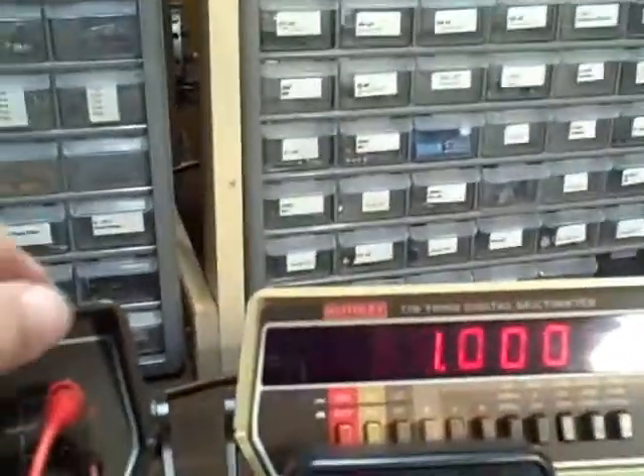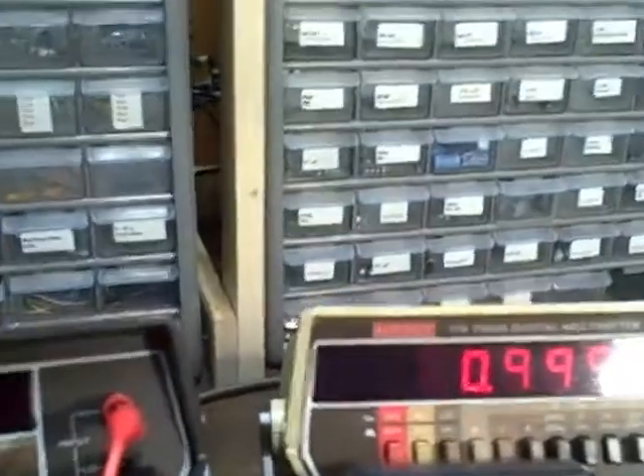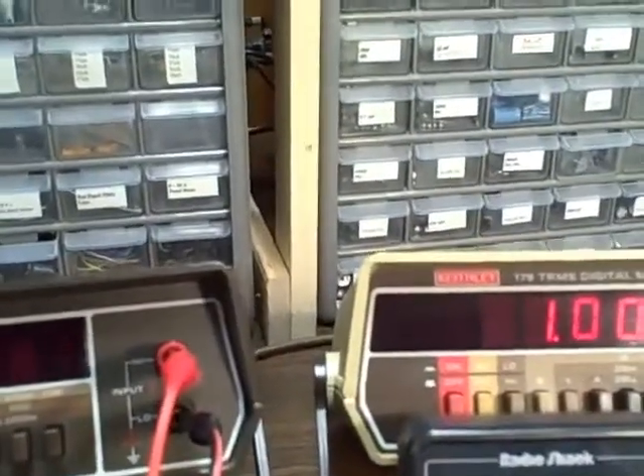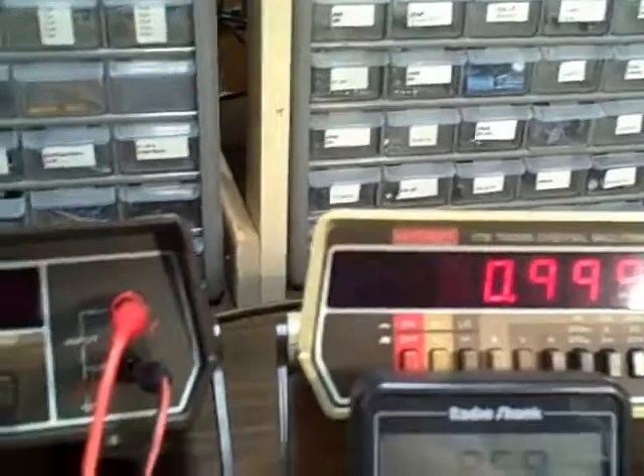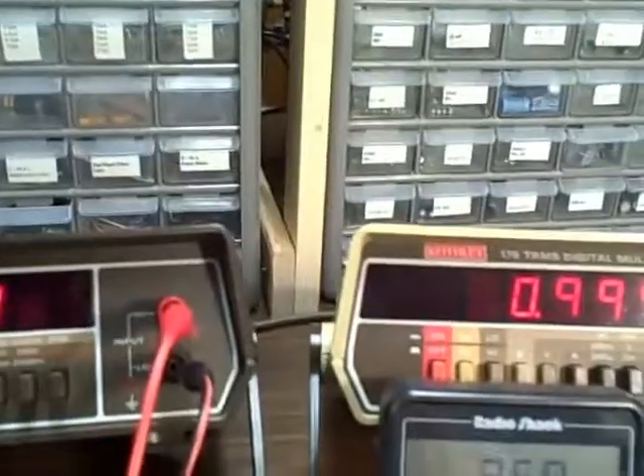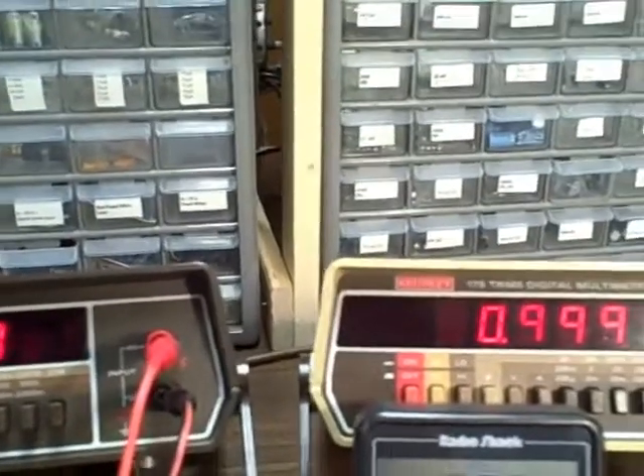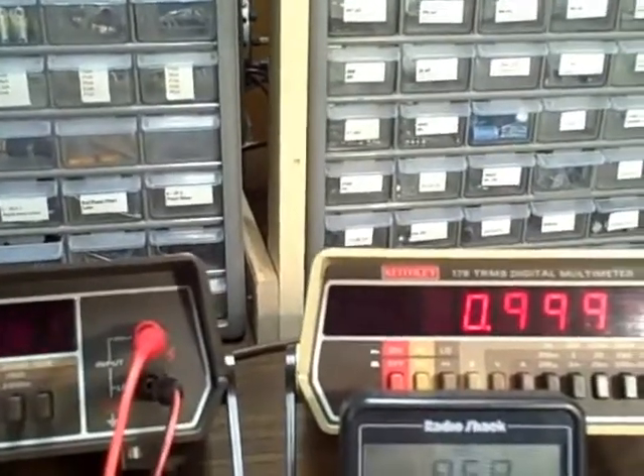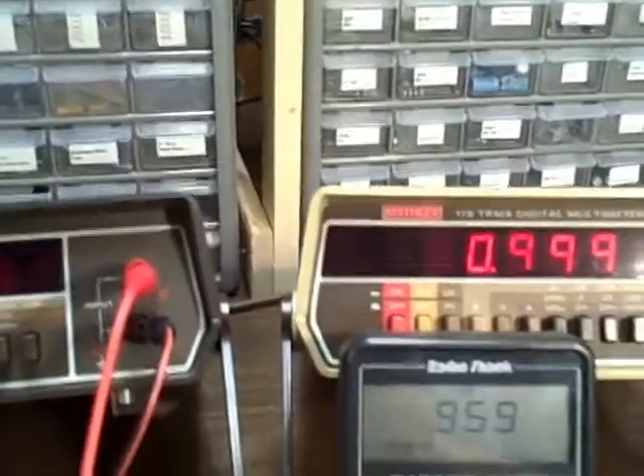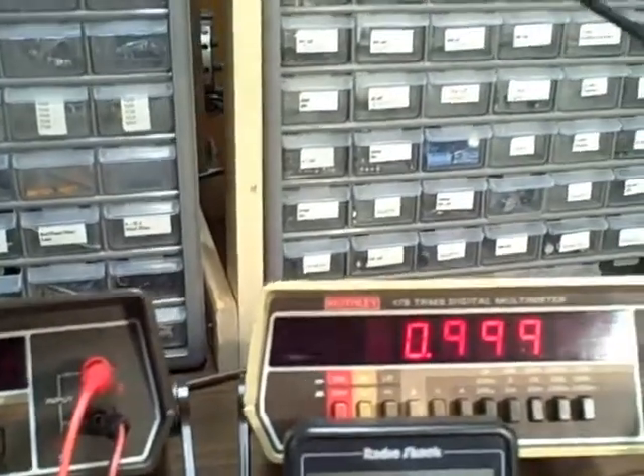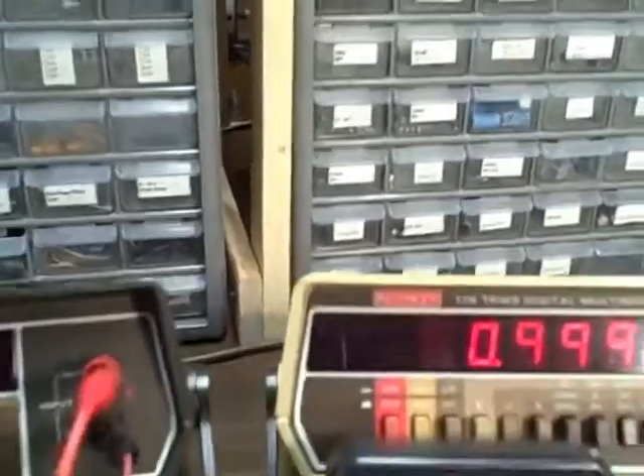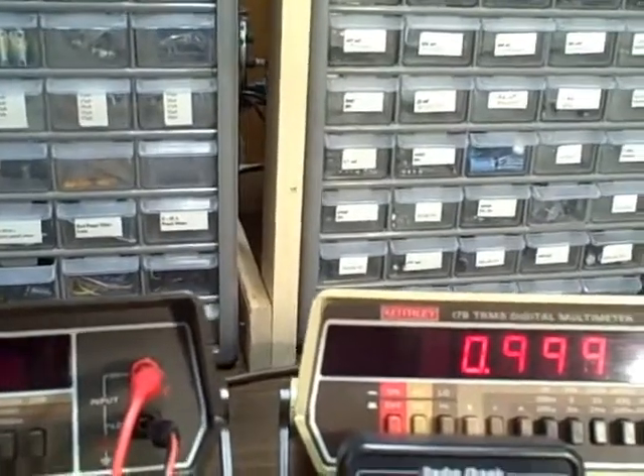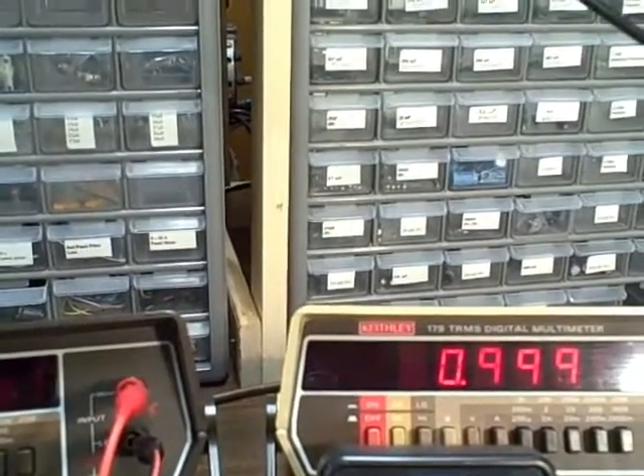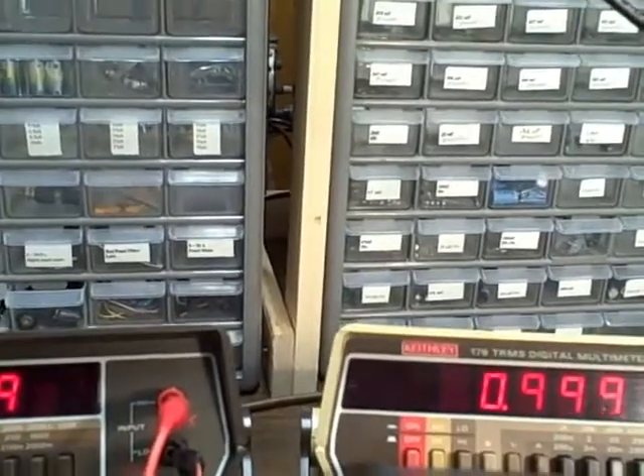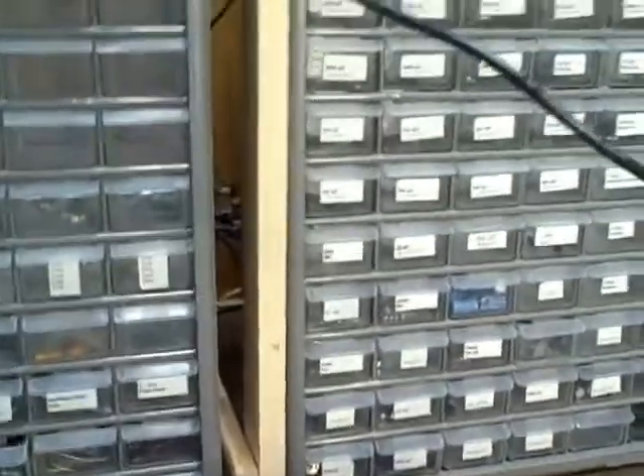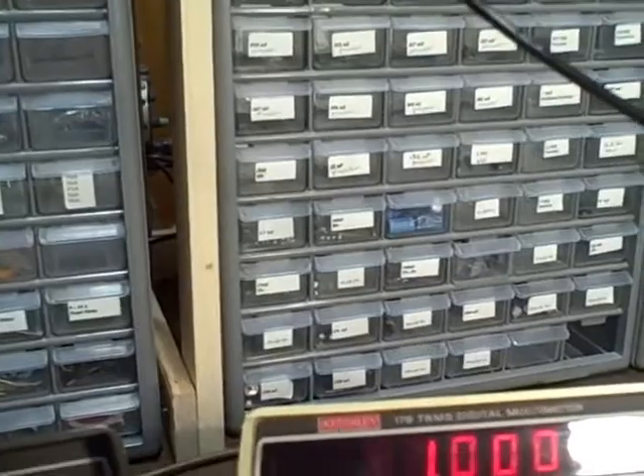We are reading the same on both of these meters, which are utilizing their AC calibration as received at the time I bought them, which would take them back to the last time they were calibrated, and I don't know when that was, but it's not my calibration, it is somebody else's, and they are in close agreement. So I'm going to use that logic to convince you that we are reading properly on the AC scale. This is on the 20 volt scale. We're going to do a quick check on the 2 volt scale.